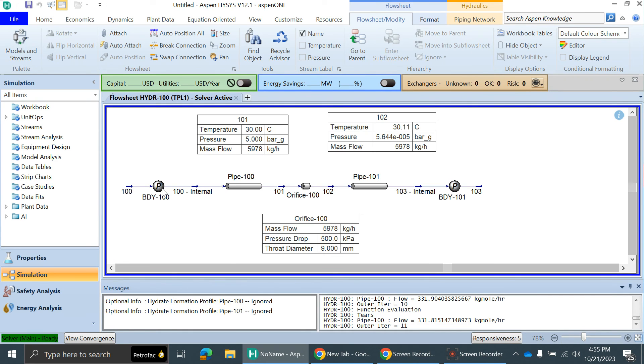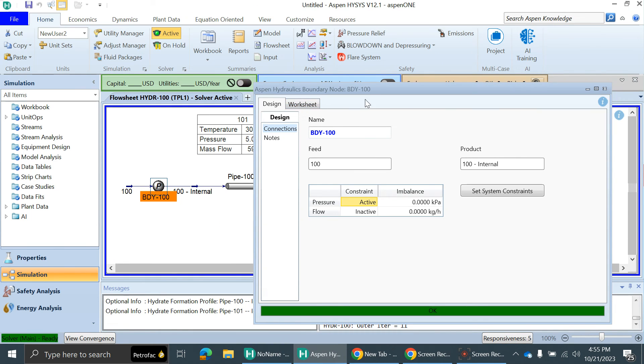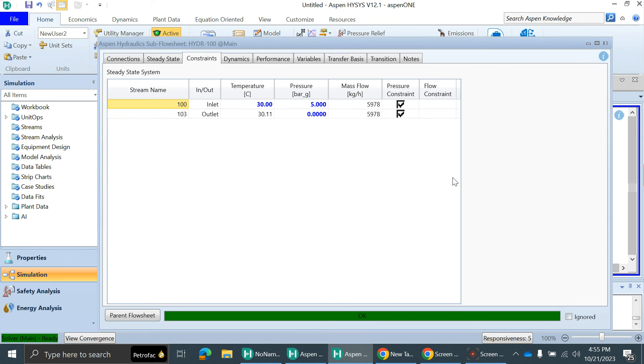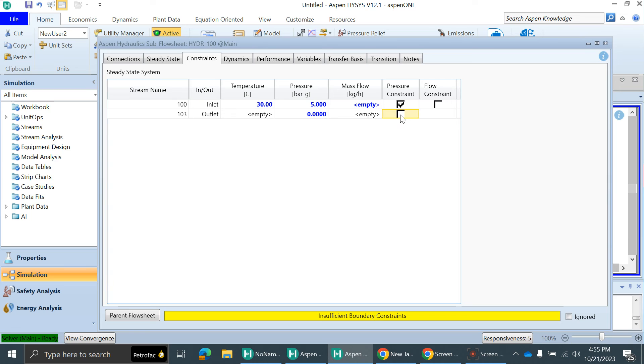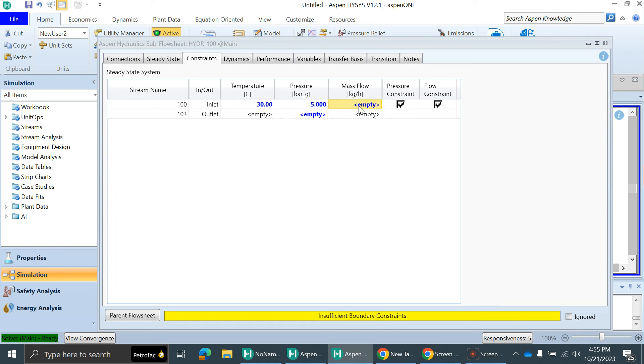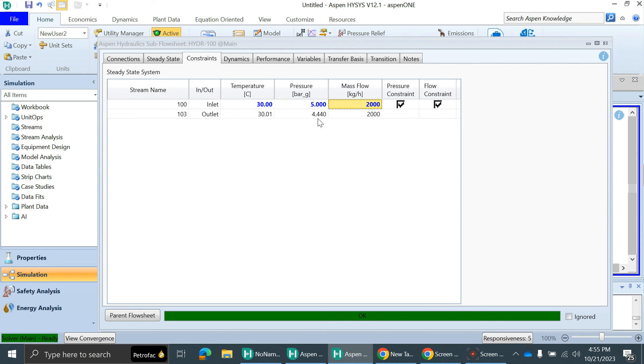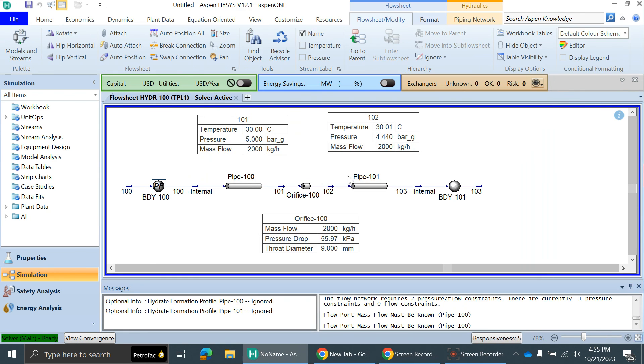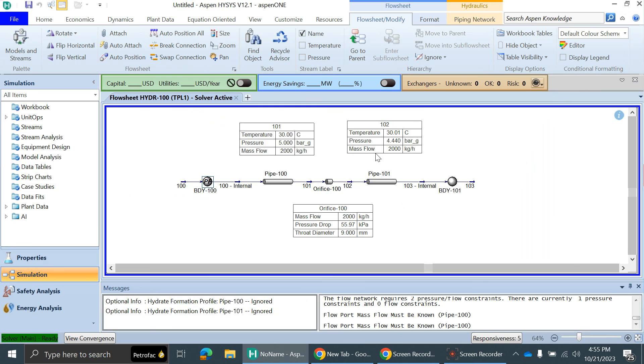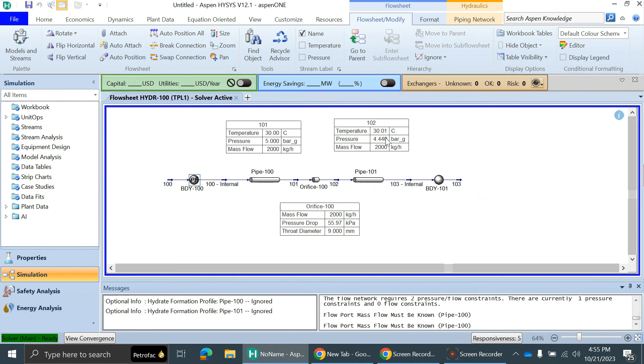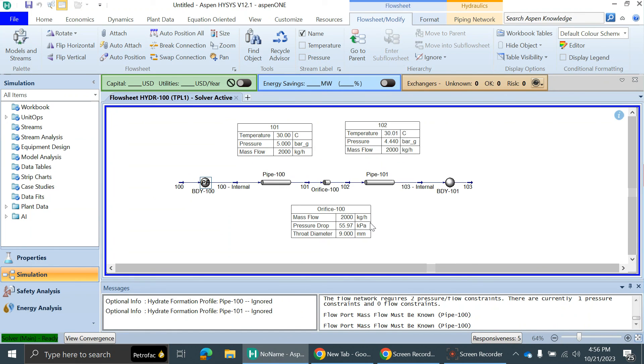Suppose you don't know the pressure at the outlet of the orifice and you know the flow. You can have the flow constraint. You can remove this pressure from here. Suppose you have 2000 kg per hour flow. You can see it will automatically give you the pressure at the outlet of the orifice. It means at this much flow and this much inlet pressure, this will be your outlet pressure of the orifice. In both ways, you can do the orifice sizing.